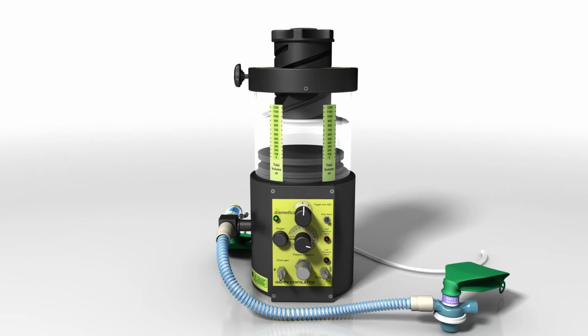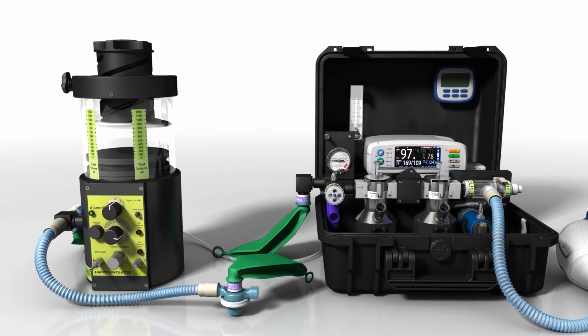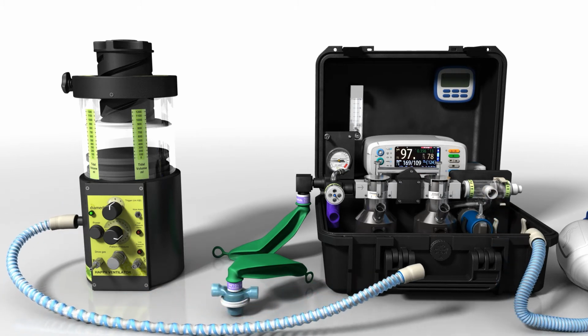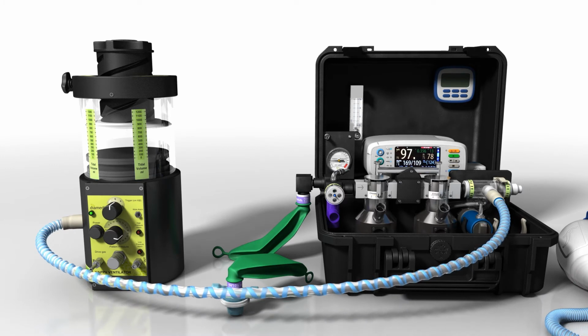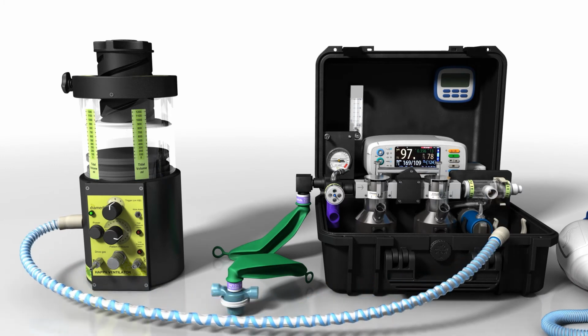The adult and paediatric ventilator was initially designed to work alongside the Diamedica portable anaesthetic systems range. If a model from the Diamedica portable anaesthetic range is being used in conjunction with the Helix portable ventilator, then the circuit block is removed and the ventilator outlet is simply connected to the DPA inspiratory valve in place of the self-inflating bag.